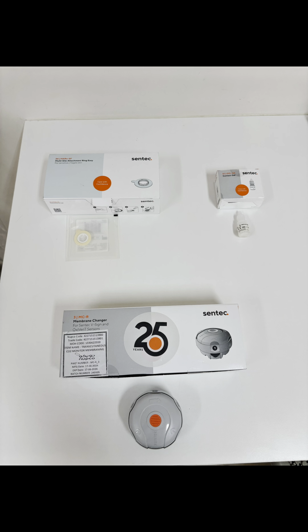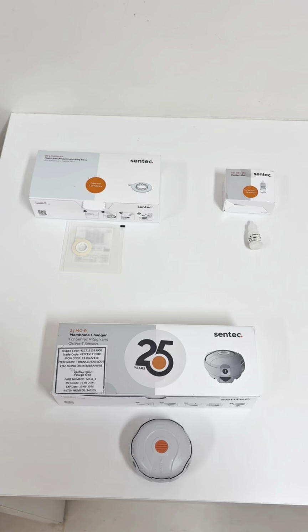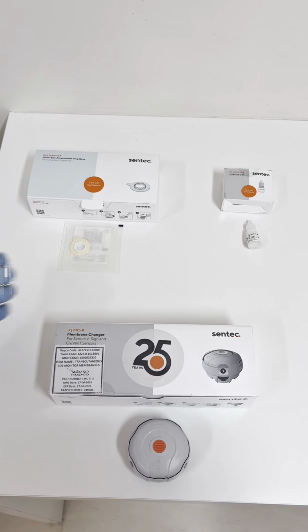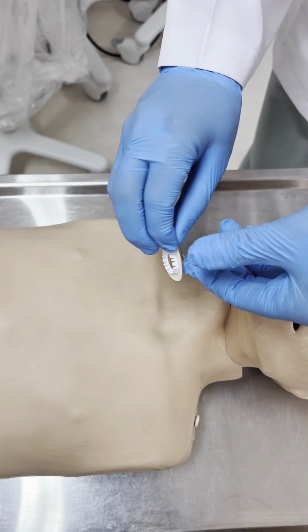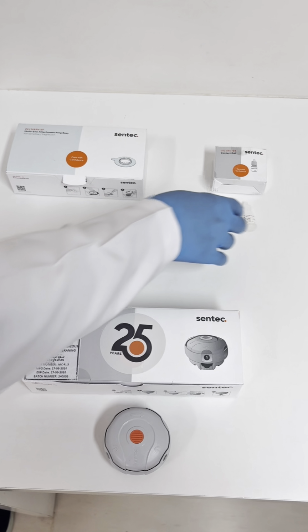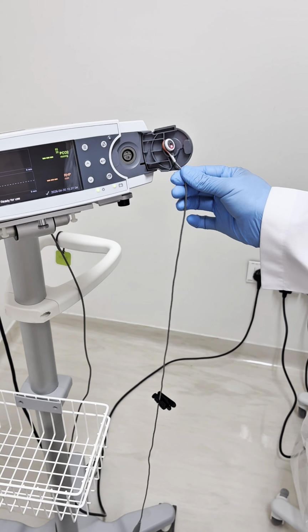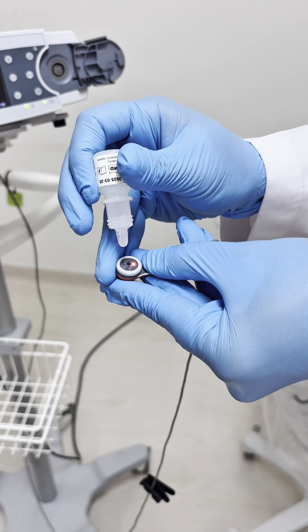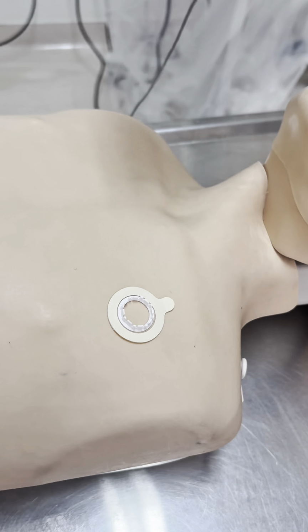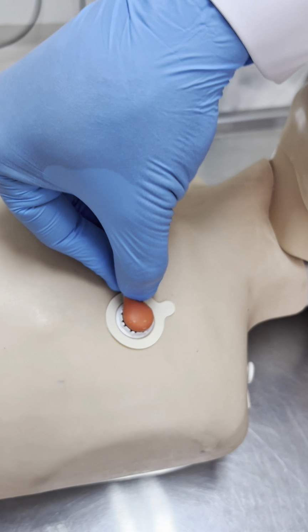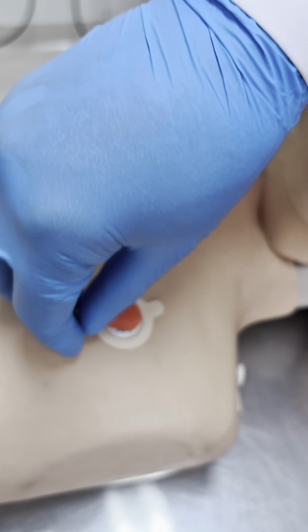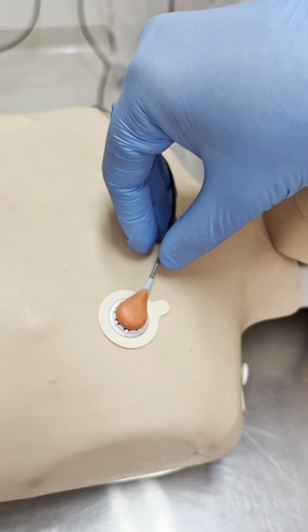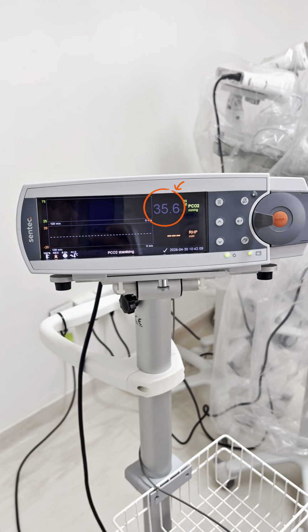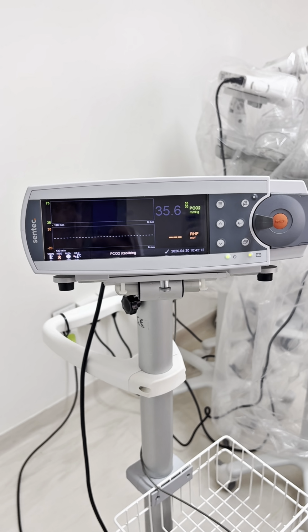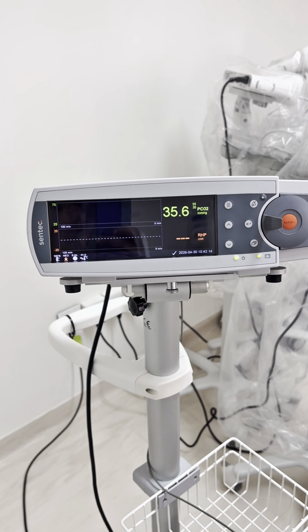Now, moving to the consumables. Attachment ring, gel, membrane changer. Now, let's start with patient application. Apply the attachment ring on the patient's skin. Apply 1 drop of the contact gel over the sensor surface. This gel will protect the patient's skin from heat and ensure the conductivity. Snap the sensor into the ring and rotate the sensor to ensure it is attached perfectly and the gel is distributed to the skin surface. Initially, the CO2 value will appear in gray color, which means it is still stabilizing, until it turns green.